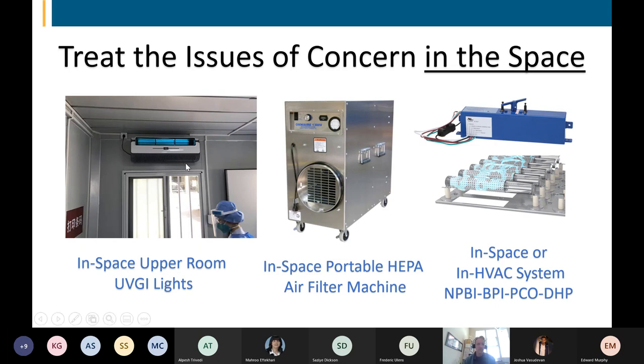On the far left-hand side of the screen, I show what's called in-space, upper room, UVGI or UVC lights. Those have been proven very effective at helping to mitigate certain contaminants of concern from the air we breathe within the space itself. It typically consists of a box, and in that box is a UVC bulb of some type, of some length, of some wattage. There's typically not a fan associated with it. You mount it at least 7 feet, if not more, above the finished floor line towards the ceiling, and you direct the louvers that are on the face of the device covering the lights to reflect upwards so that its luminance, or the photons that are emitted to the air, are directed upward.